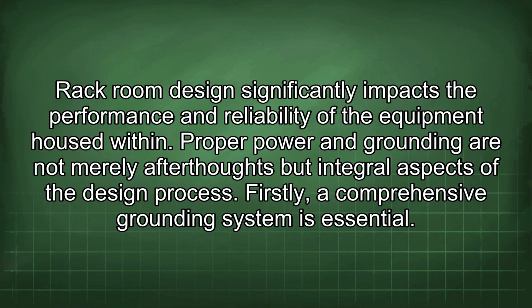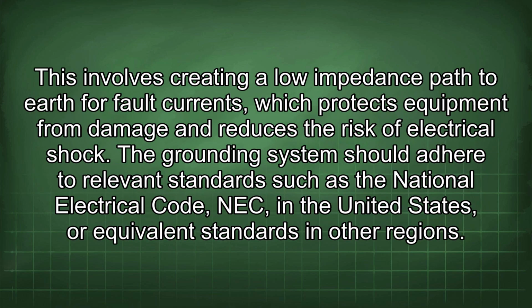Firstly, a comprehensive grounding system is essential. This involves creating a low impedance path to earth for fault currents, which protects equipment from damage and reduces the risk of electrical shock. The grounding system should adhere to relevant standards such as the National Electrical Code, NEC, in the United States, or equivalent standards in other regions.